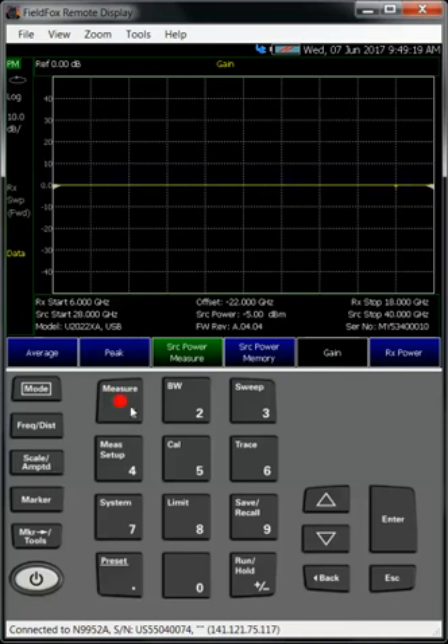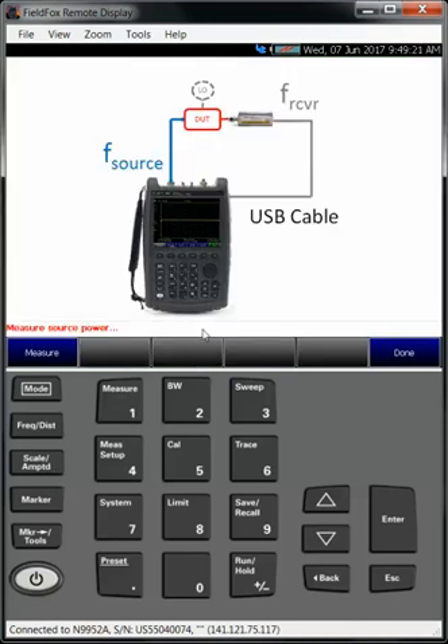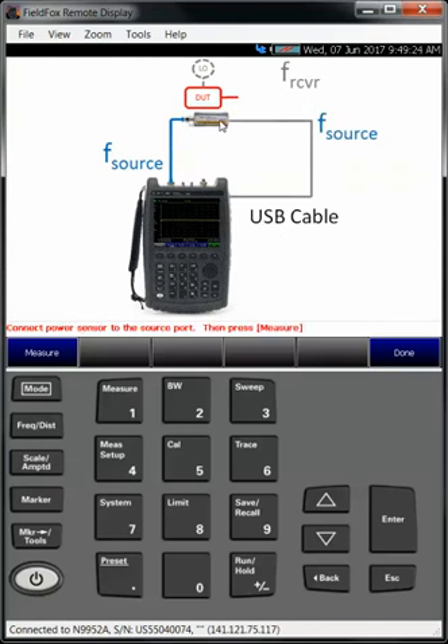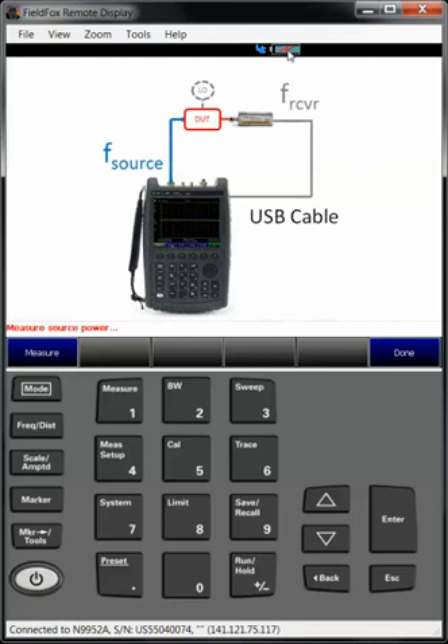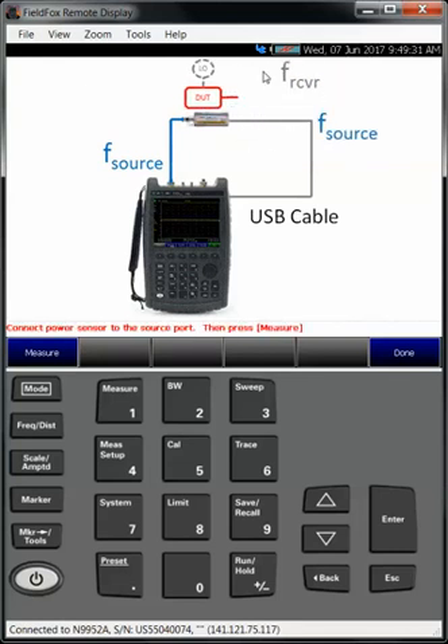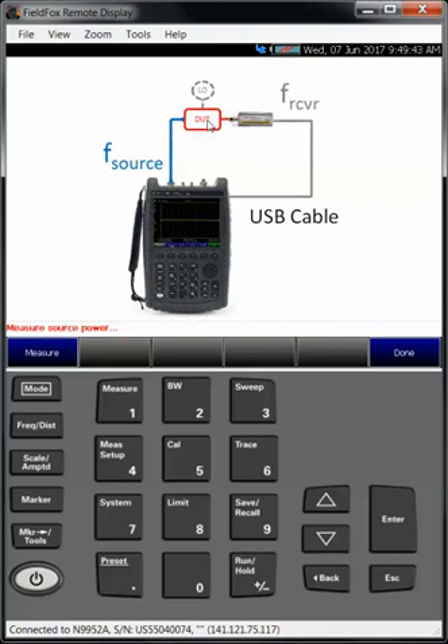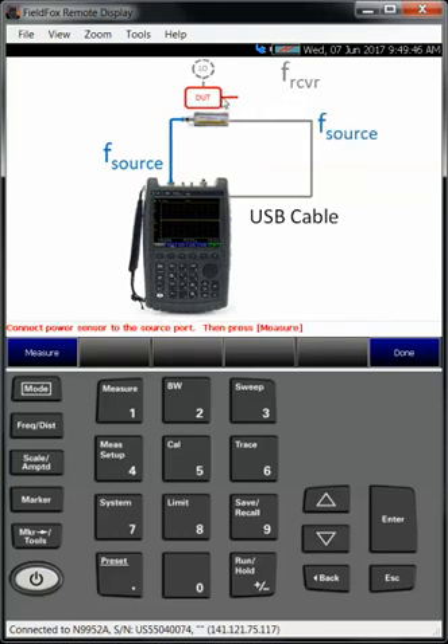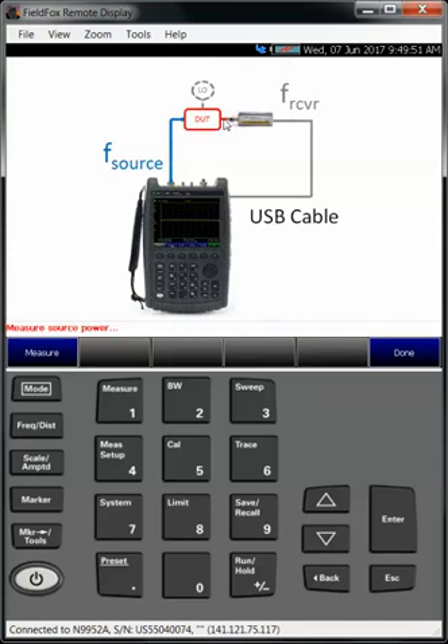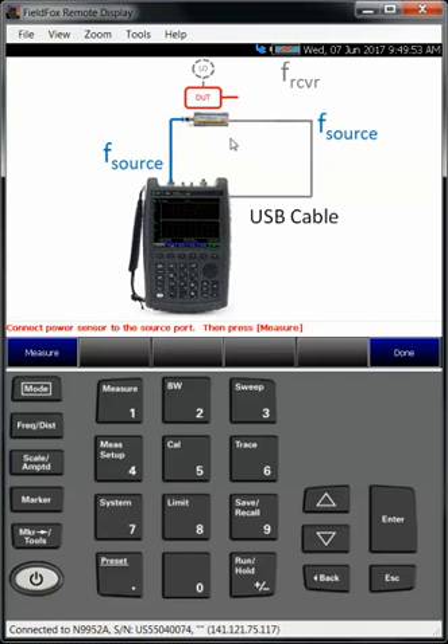And I just want to show you this diagram. The assumption is that the sensor is going to the DUT output. If you have a cable, if you have something on the output that is between the DUT and where your sensor goes, that's not really getting corrected for. I think that's the question of, is there any calibration on the receiver frequencies? And there isn't, because the assumption is that the power sensor is connected directly to the DUT output. And so the measurements are accurate. So that's in your B over R, it's this R measurement at the receive frequency.